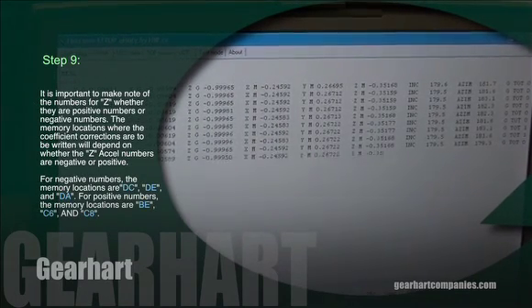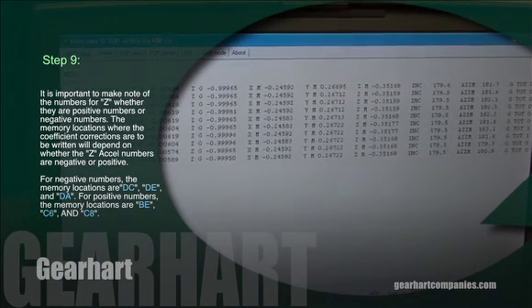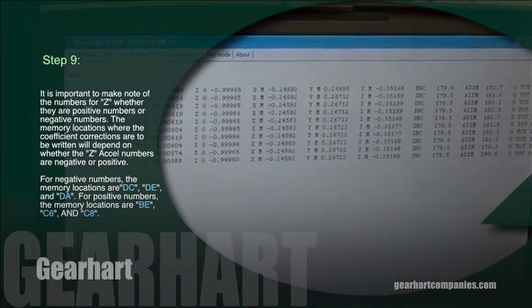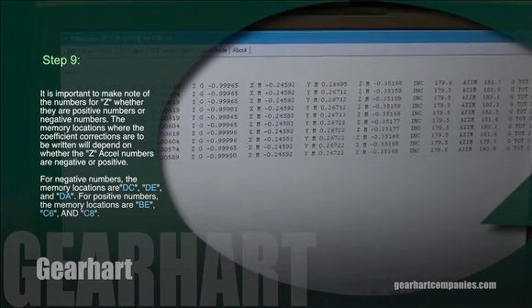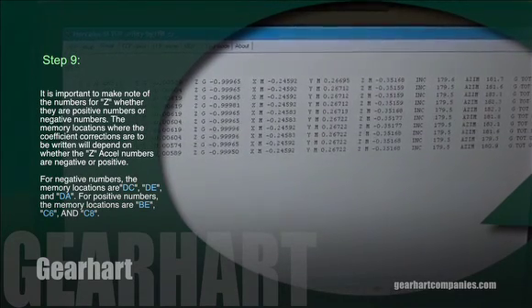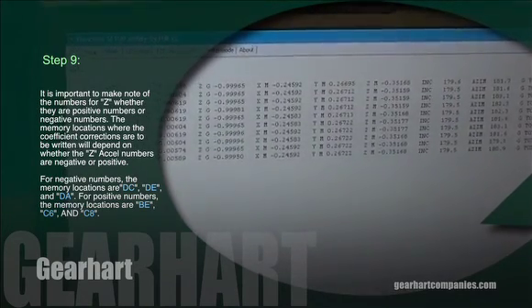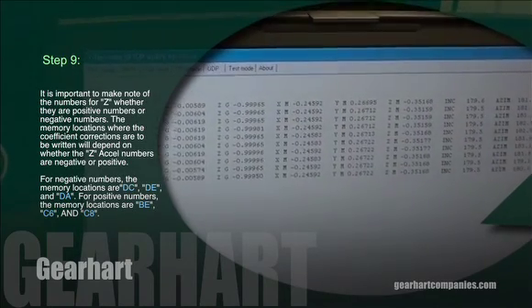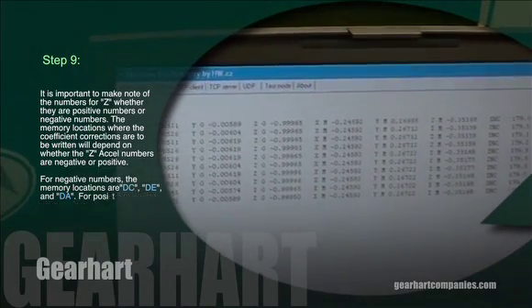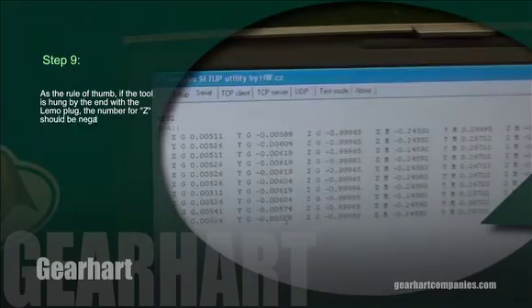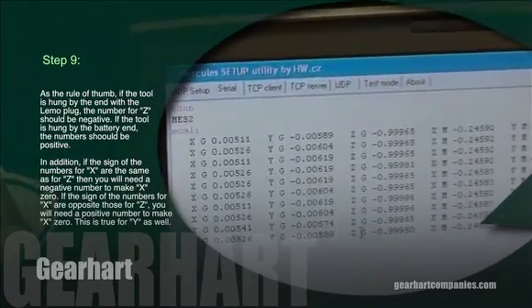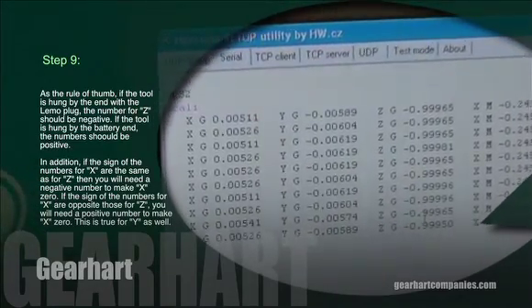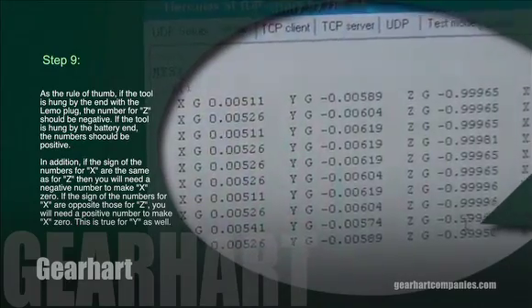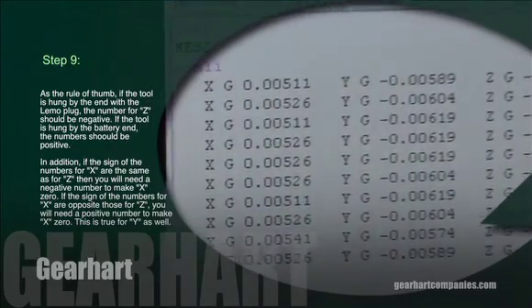The memory locations where the coefficient corrections are to be written will depend on whether the Z accel numbers are negative or positive. For the negative numbers, the memory locations are DC, DE, and DA. For the positive numbers, the memory locations are BE, C6, and C8. As the rule of thumb, if the tool is hung by the end with the Lemo plug, the number for Z should be negative. If the tool is hung by the battery end, the number should be positive.